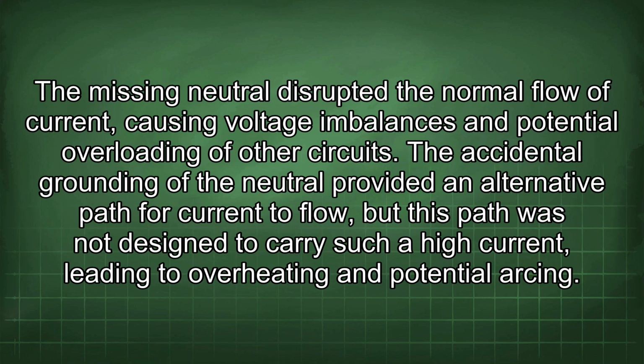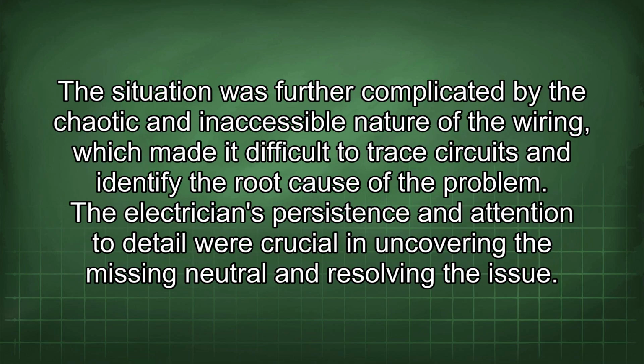The missing neutral disrupted the normal flow of current, causing voltage imbalances and potential overloading of other circuits. The accidental grounding of the neutral provided an alternative path for current to flow, but this path was not designed to carry such a high current, leading to overheating and potential arcing. The situation was further complicated by the chaotic and inaccessible nature of the wiring, which made it difficult to trace circuits and identify the root cause of the problem.